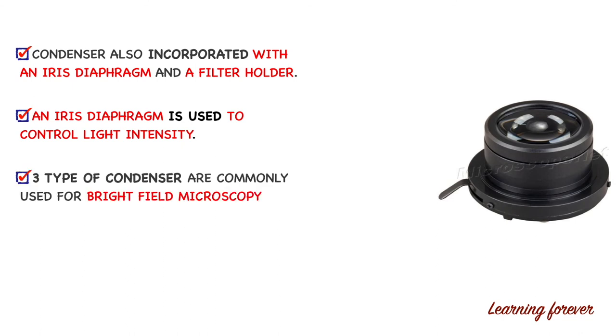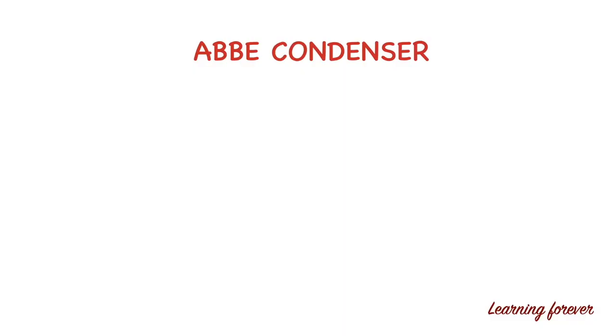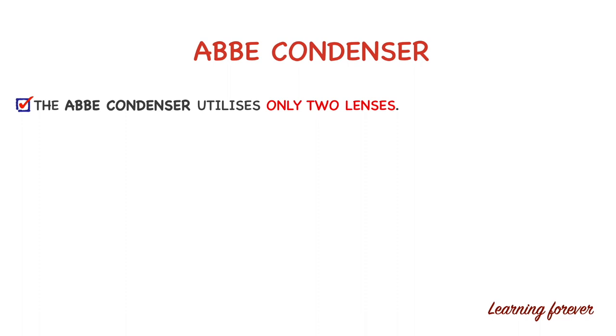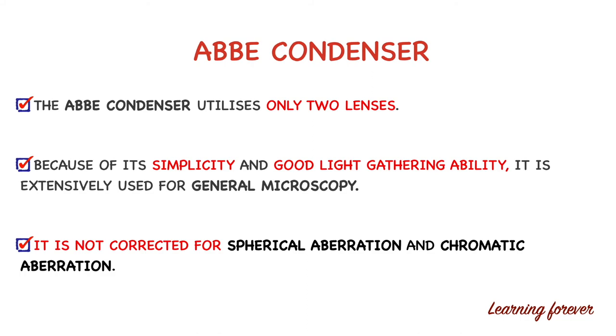There are three types of condenser used for bright field microscopy. First is the Abbe condenser, which uses only two lens systems. Due to its simplicity and good light-gathering ability, it is extensively used for general microscopy, though it is not corrected for spherical or chromatic aberration. Second is the variable focus condenser, which consists of two lens systems where the upper lens element is fixed and the lower lens element is flexible, allowing it to move up and down to achieve variable focus. This condenser is essentially similar to the Abbe condenser when the lower lens is raised to its top position.